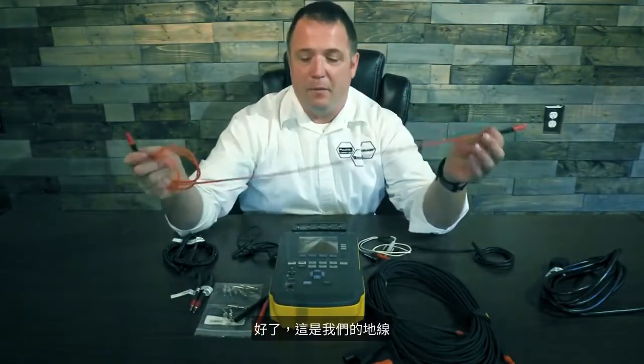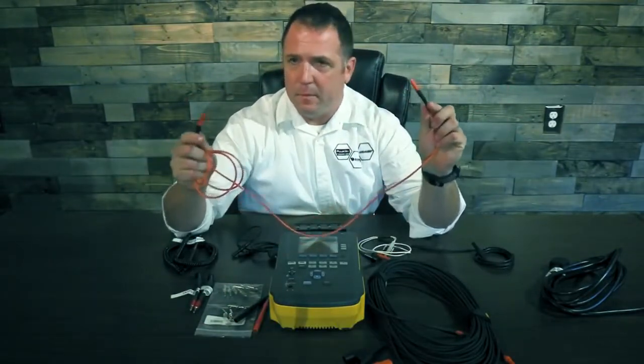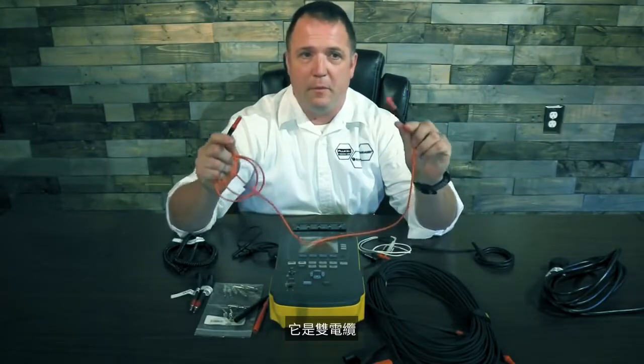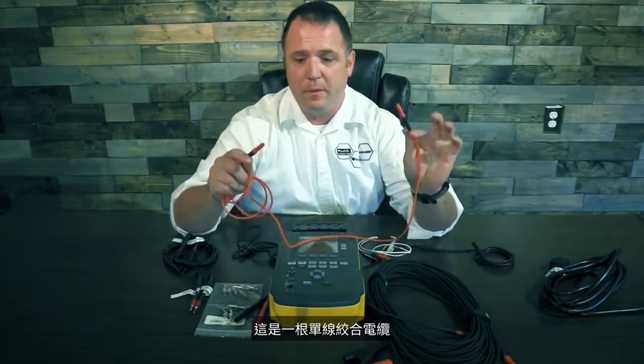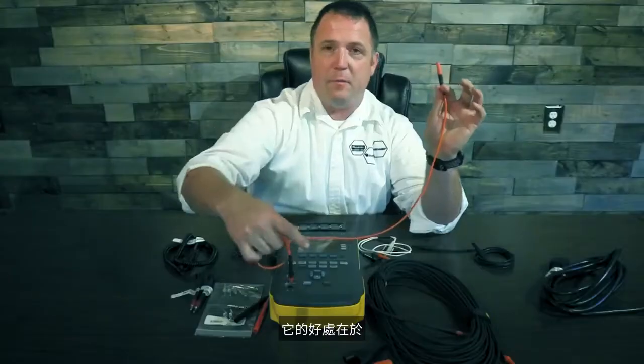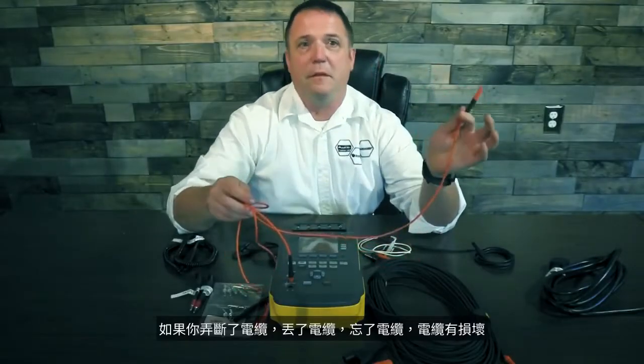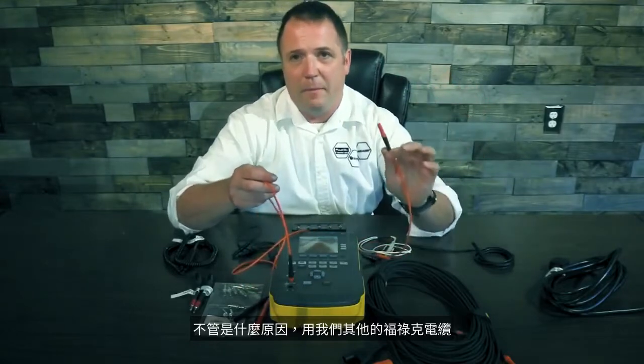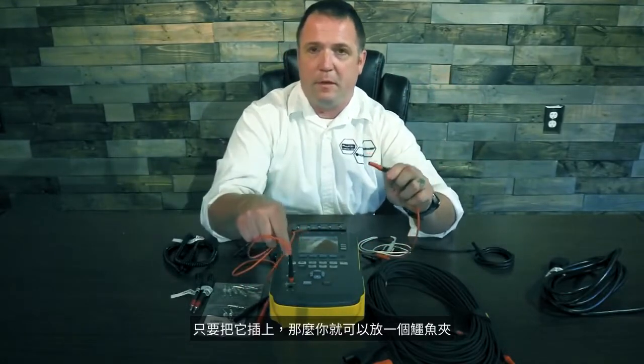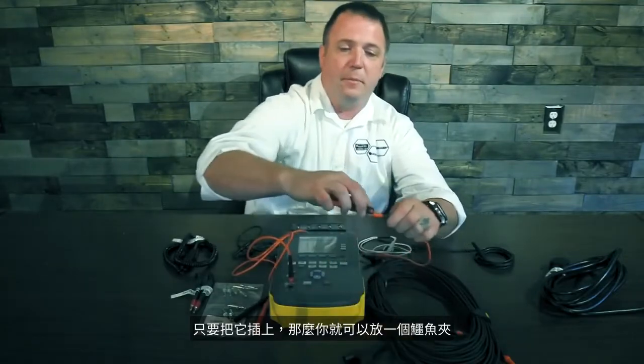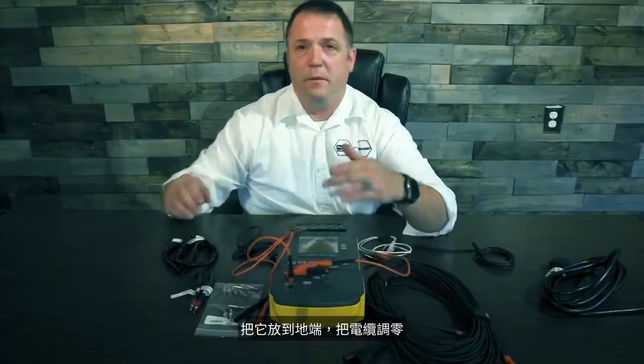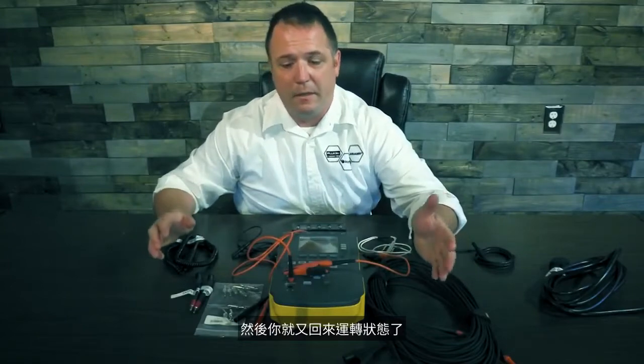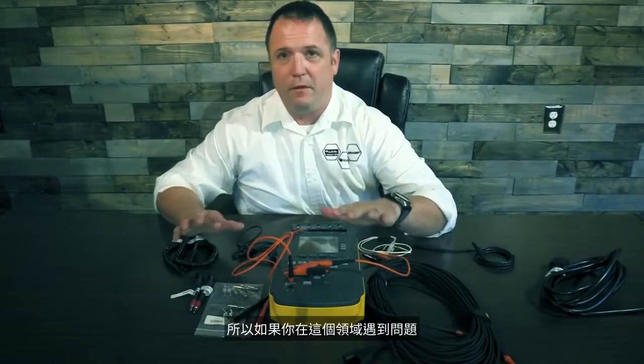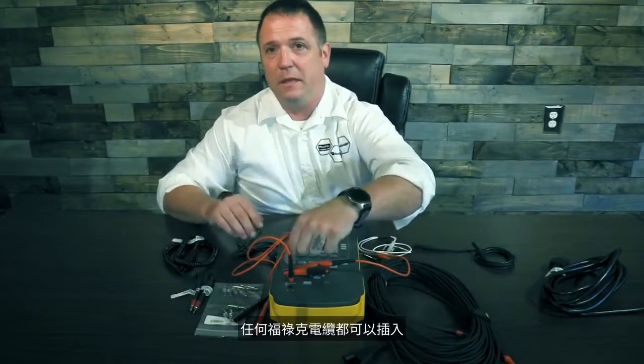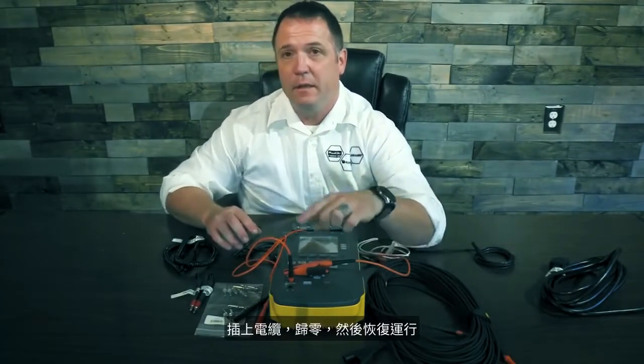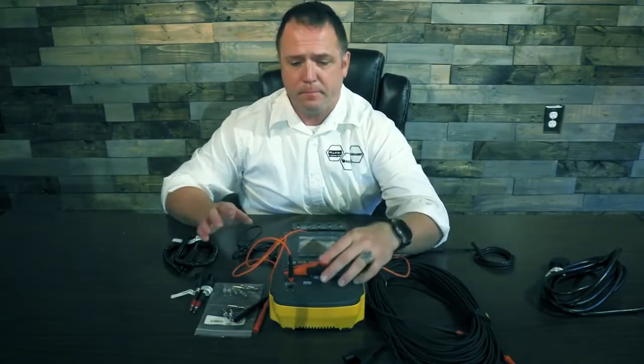All right, now this is our ground cable. Before we used to use a Kelvin cable, which is a dual cable. This is a single wire stranded cable. So what's nice about that, if you break the cable, lose the cable, forget the cable, whatever the reason, grab any of our other Fluke cables, simply plug it in, then you can put on an alligator clip and take it to the ground and zero out the cable and you're back up and running. It makes it super easy, so if you ever have an issue in the field, any Fluke cable will plug in, or one off your multimeter maybe, plug in, zero it out, and back up and running.